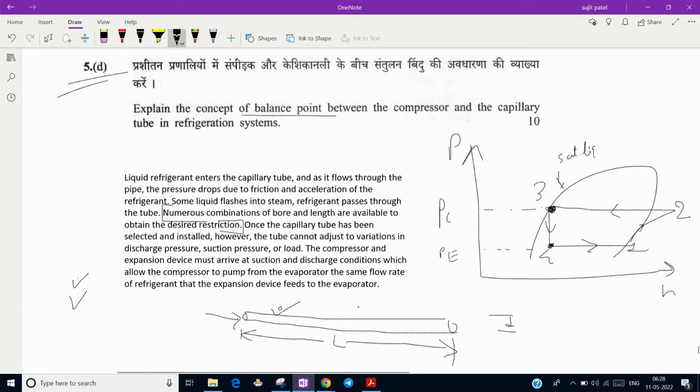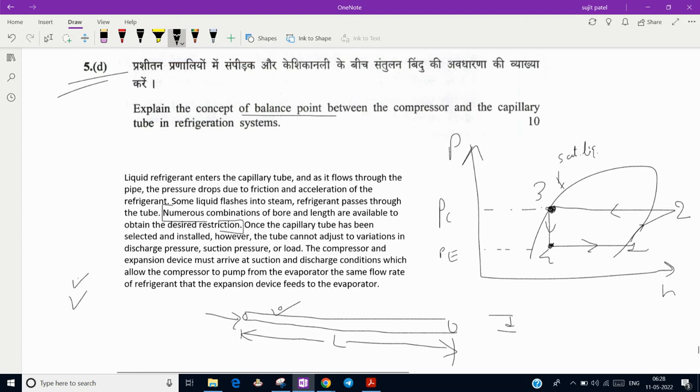the capillary tube cannot adjust the variation in discharge pressure and suction pressure. If there is variation in suction, discharge or load condition, it will not sustain because capillary is a fixed opening type, not like thermostatic expansion valve.